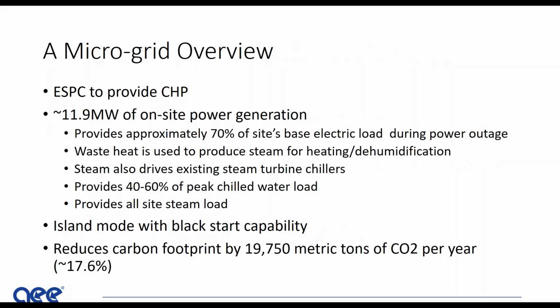So we put a microgrid in - basically about 11, almost 12 megawatts of power. It's on-site power generation with 2 solar turbines. It provides about 70% of this particular site - not set here, but it's Johnson Space Flight Center in Houston, which we back up - providing about 70% of the site's base load during a power outage. We use the waste heat from the turbines through a heat recovery steam generator to produce steam for heating and dehumidification as well. We can also provide steam to run some steam turbine chillers, which can provide about 50% of the peak chilled water load, and provides all the site steam load needed. It can also enable black start capability and reduce the carbon footprint, since it's much more efficient than what they were doing before.